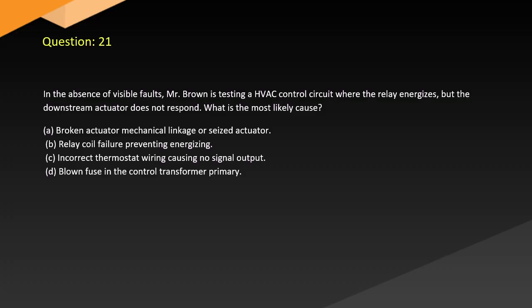Question 21. In the absence of visible faults, Mr. Brown is testing a control circuit where the relay energizes but the downstream actuator does not respond. What is the most likely cause? A. Broken actuator mechanical linkage or seized actuator. B. Relay coil failure preventing energizing. C. Incorrect thermostat wiring causing no signal output. D. Blown fuse in the control transformer primary.